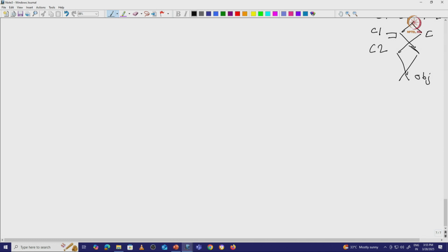So if we consider that there is a C1 lens and there is a C2 lens, last class I discussed only the C1 lens, that there will be a crossover point and it is changing. If this is the crossover point from the C1 lens, what changes is the position of this crossover point. But if you look at this diagram, you can see in all the cases that the C1 lens is regulating how much electron dose is going through the C2 lens. So now we'll draw the same diagram again.